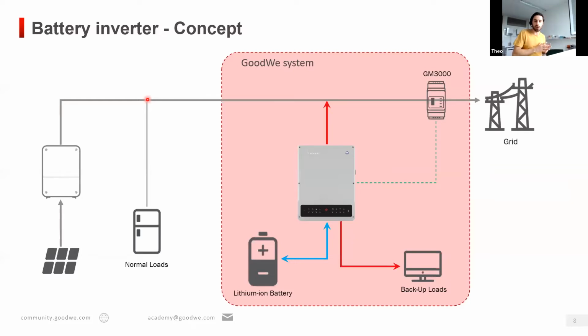And let's say that a few years ago you installed this PV system. At this moment, maybe you didn't want to have a storage, but now a few years later, you think, oh, now I really want to have a storage, but instead of swapping this inverter to a hybrid inverter that we saw before, it's possible to use our battery inverter concept. This is an AC retrofit solution. So it looks similar to our hybrid inverters, but they don't have any input for PV. So it's a pure battery inverter that connects here on the AC side, takes the AC power here, charges the battery, and then back and forth. So in this way, you can utilize the energy produced by the PV here, charge the battery, and then output it again on the AC line.